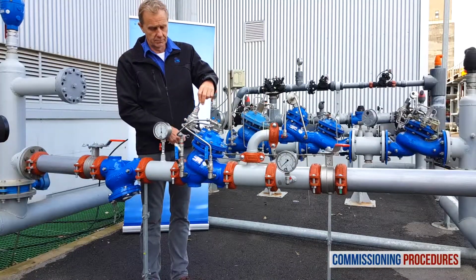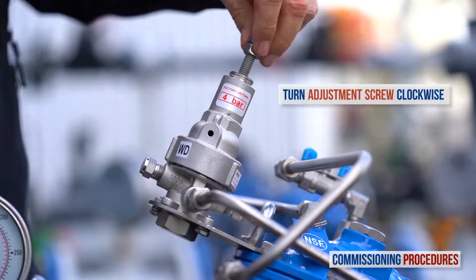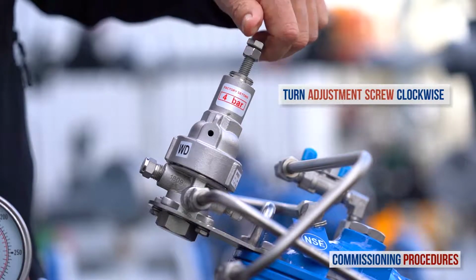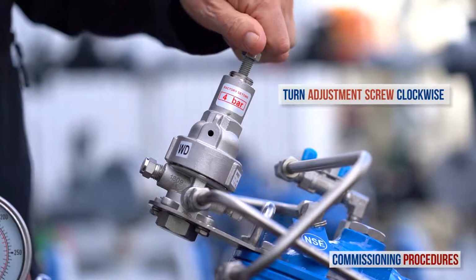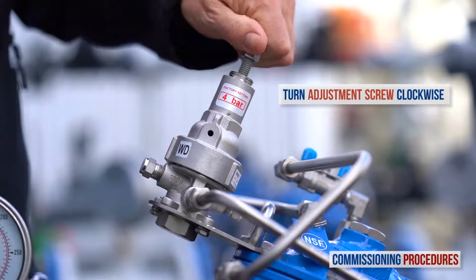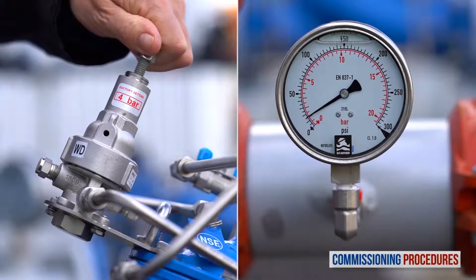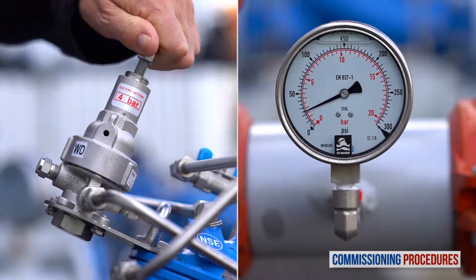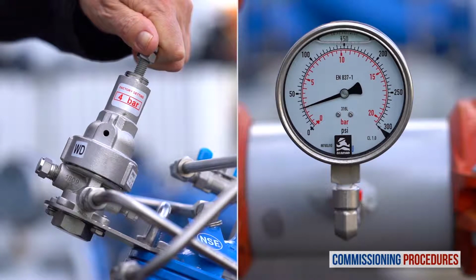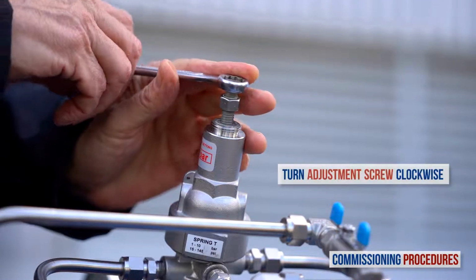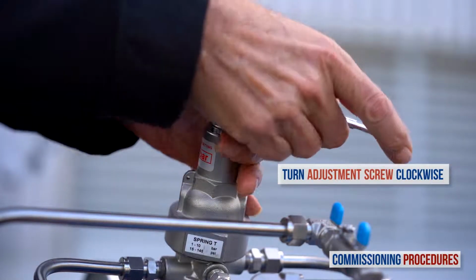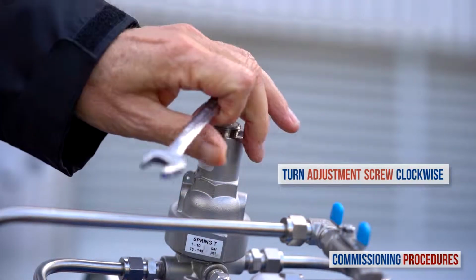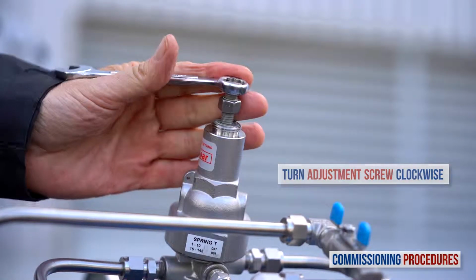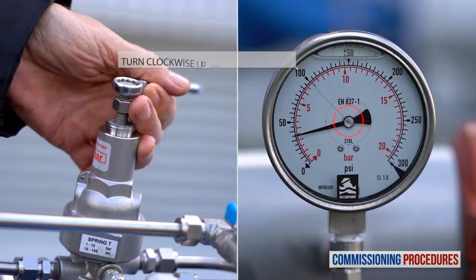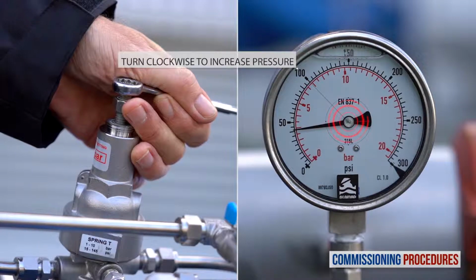Begin the pressure calibration process by slowly turning the reducing valve's pilot adjustment screw clockwise until you hear the valve opening or feel a resistance at the pilot adjustment screw. At this point, the downstream consumer's pipeline will start to fill. When the consumer's pipeline is full, slowly turn the adjustment screw clockwise to increase downstream pressure while monitoring the downstream pressure gauge until you reach the required pressure.